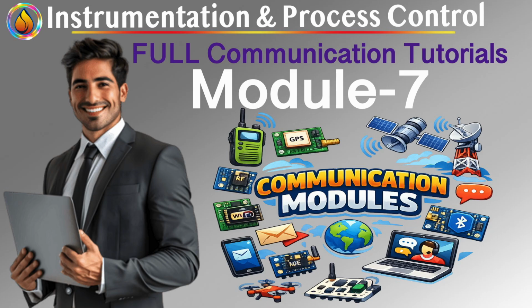Control without a PLC: what that really means. Let's be precise here. Foundation Fieldbus does not say, "PLCs are obsolete." It says, "PLCs are no longer the only place control can live." That distinction matters. PLCs still excel at sequencing, interlocks, high-speed logic, and complex state machines. Foundation Fieldbus excels at continuous control, process loops, distributed execution, and resilient architectures. They are different tools for different layers of control.